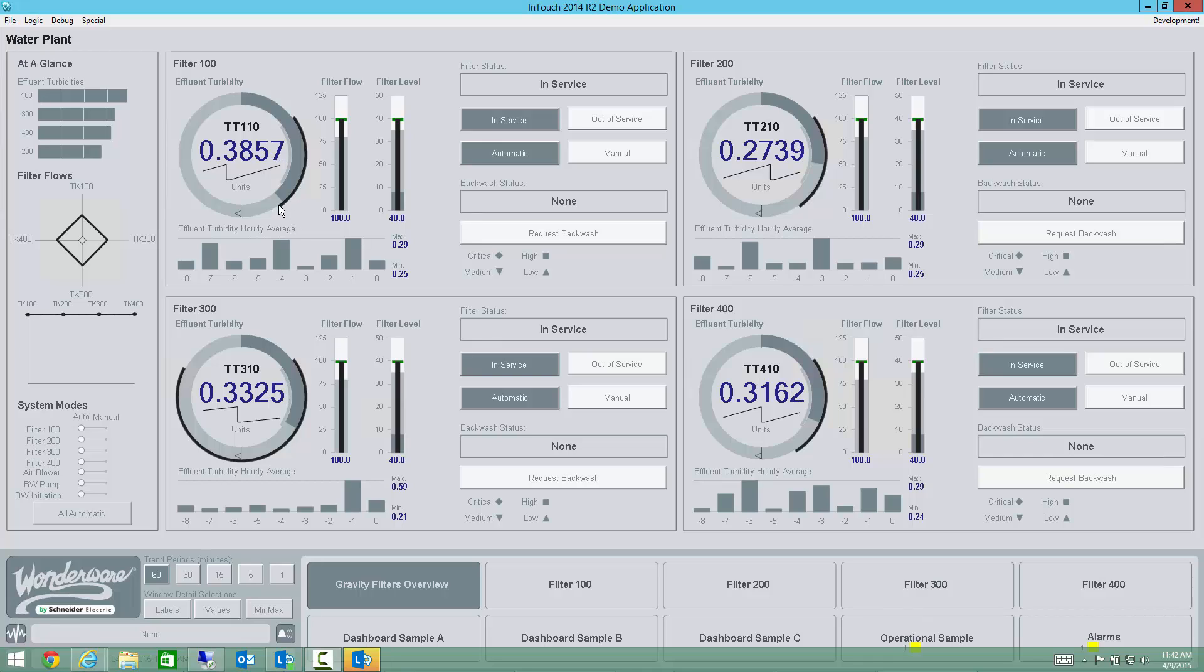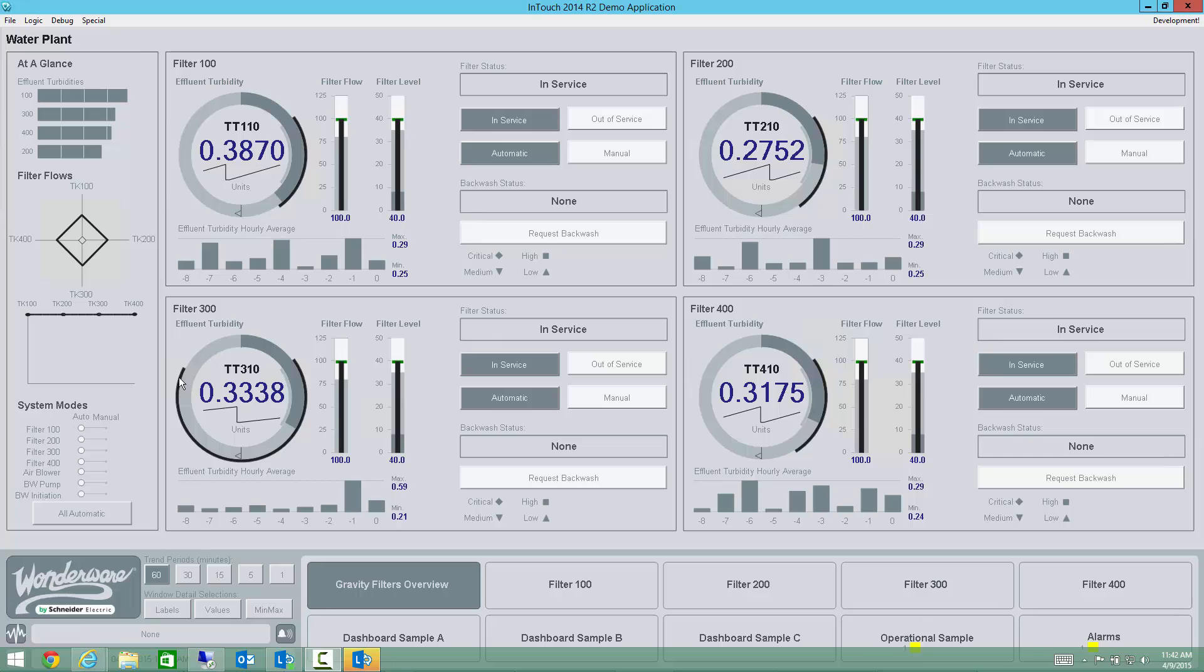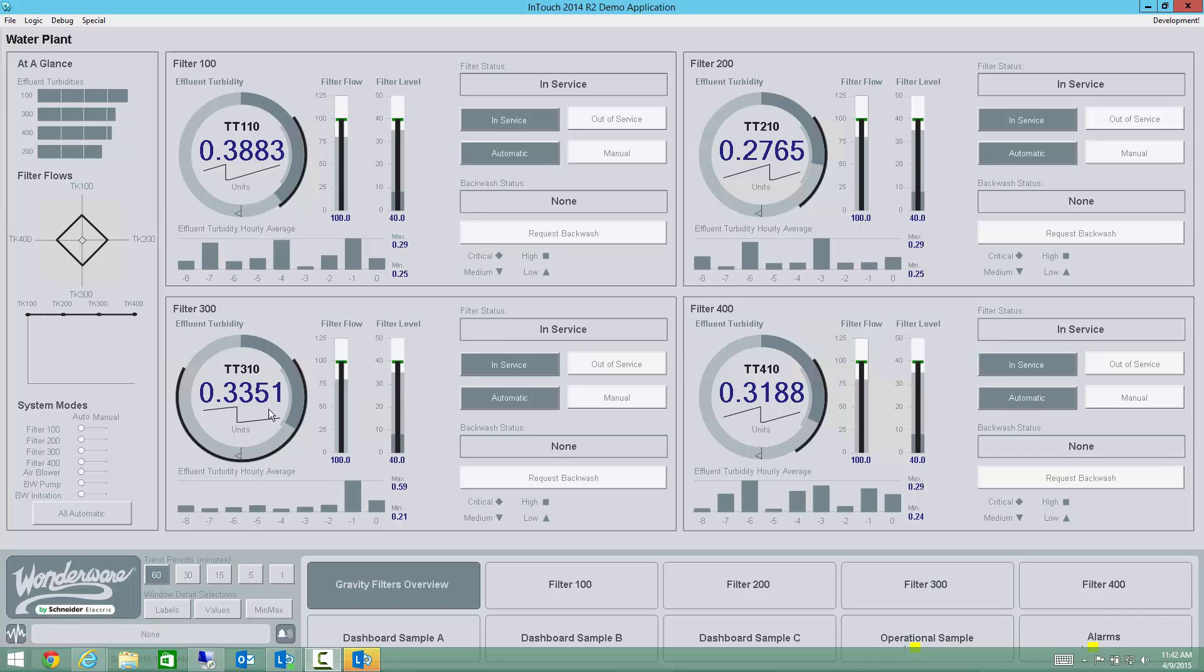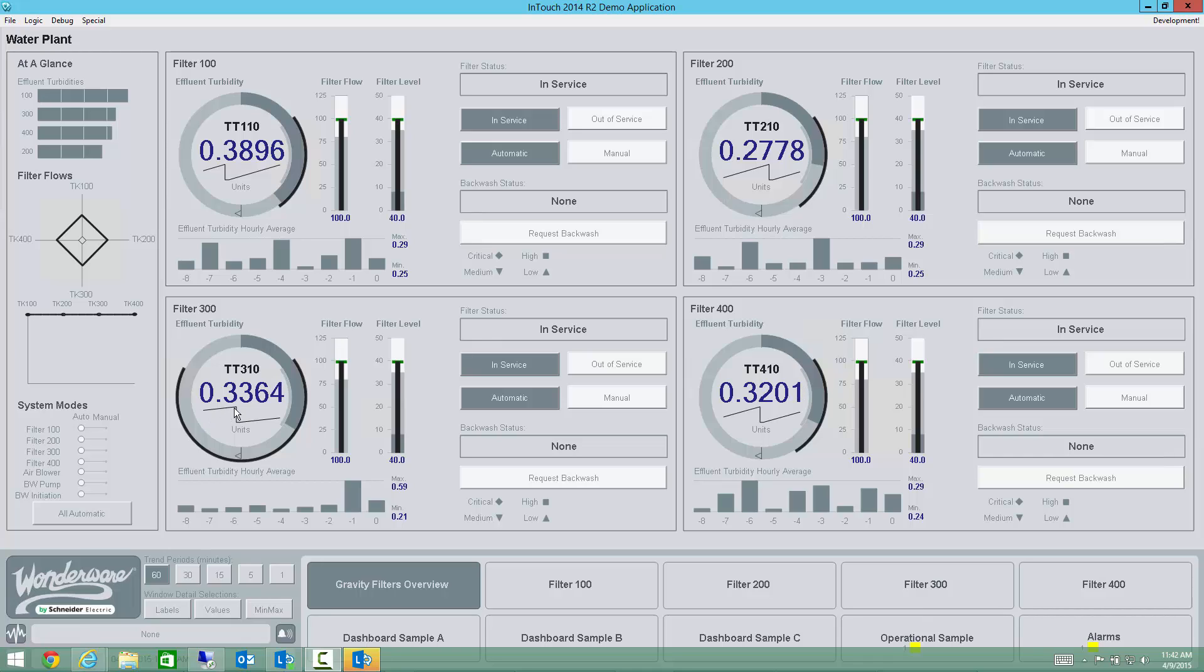And I can see that in this particular unit, it's been higher than it is now in the last hour. If I look at some of the other units, they're similarly behaving except for 300. In the unit 300, I can say that something must have gone pretty bad because not only was it outside of the expected limits. Here's an alarm flag, which is showing me the high alarm. So this went well outside its high alarm in the last hour. It's fine now in terms of the way it's operating. It's still within the operational limits I'm expecting for now. But you can see in the last hour, and based on this trend, you can see about where it occurred. Probably just a little over half an hour ago, I had reached that spike that had sent me up into that high area.